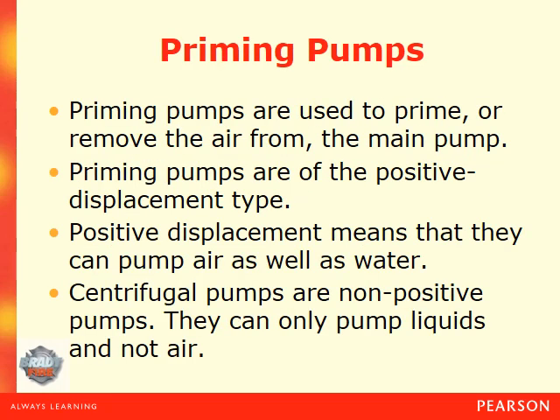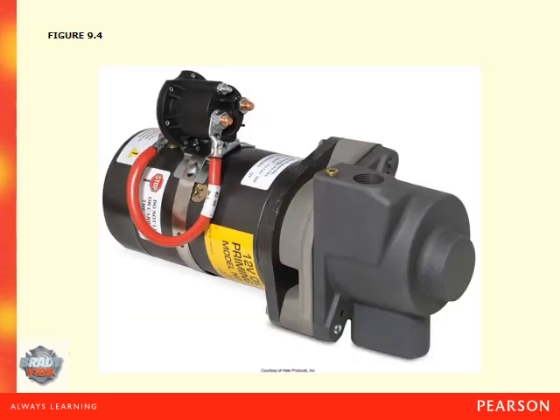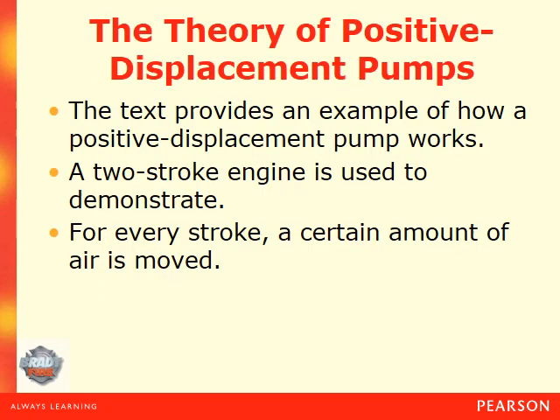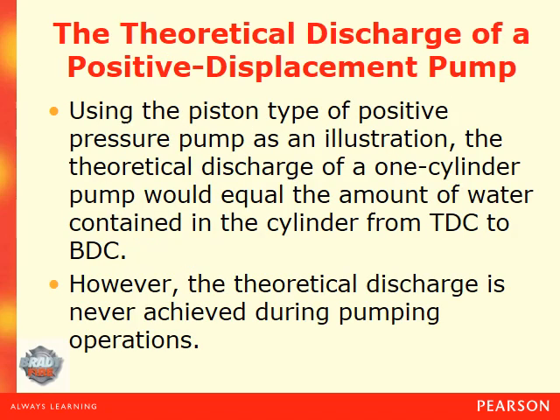Priming pumps are used to prime or remove the air from the main pump. Priming pumps are of the positive displacement type, meaning they can pump air as well as water. Centrifugal pumps are non-positive pumps — they can only pump liquids and not air. The text provides an example using a two-stroke engine to demonstrate how a positive displacement pump works: for every stroke, a certain amount of air is moved. The theoretical discharge of a one-cylinder pump equals the amount of water contained in the cylinder from TDC to BDC. However, the theoretical discharge is never achieved during pumping operations.